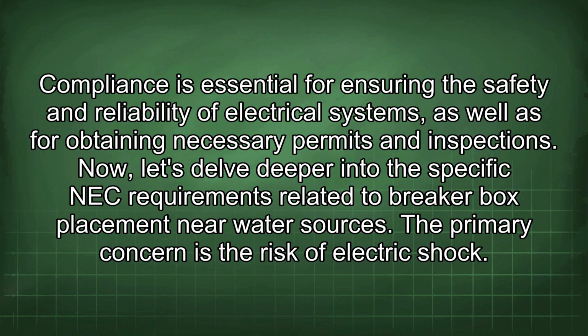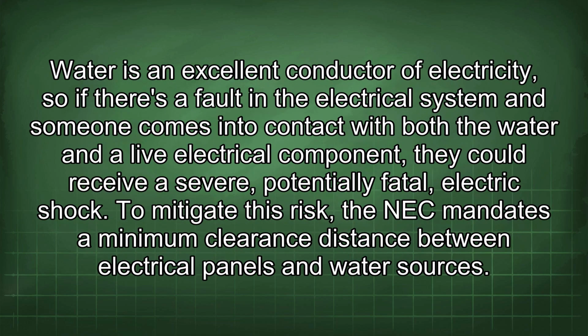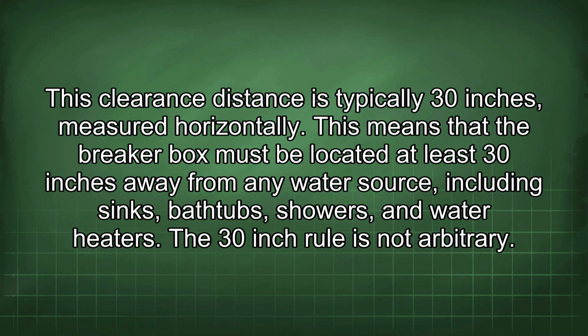The primary concern is the risk of electric shock. Water is an excellent conductor of electricity, so if there's a fault in the electrical system and someone comes into contact with both a water and a live electrical component, they could receive a severe, potentially fatal electric shock. To mitigate this risk, the NEC mandates a minimum clearance distance between electrical panels and water sources. This clearance distance is typically 30 inches, measured horizontally.